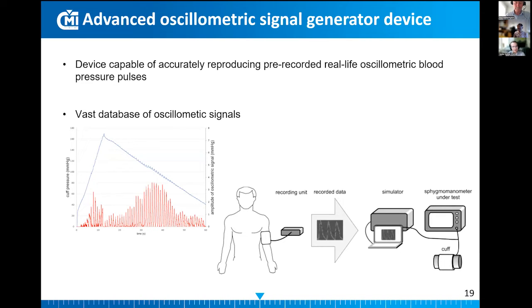Going into more detail about the advanced oscillometric signal generator, as I mentioned, the keystone is a database of oscillometric signals. Here is a schema of how it all works. Oscillometric signals are small pressure oscillations of low amplitude, usually between 4 and 10% of cuff pressure. And these are recorded by the recording unit and stored in a computer and further used in the simulator or in our advanced oscillometric signal generator. Our project uses a vast database of oscillometric signals that were previously collected by Newcastle University about 20 years ago. The database contains about 1,300 signals from approximately 600 patients.